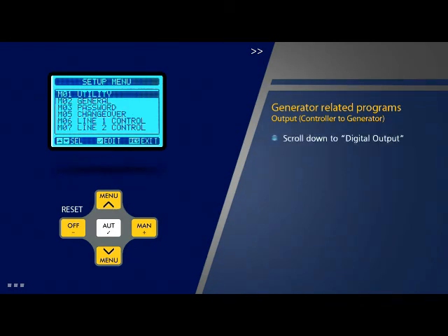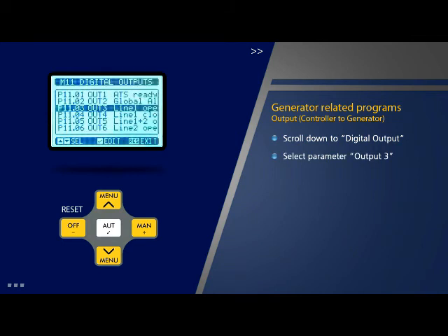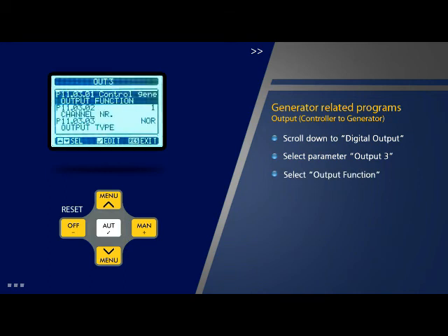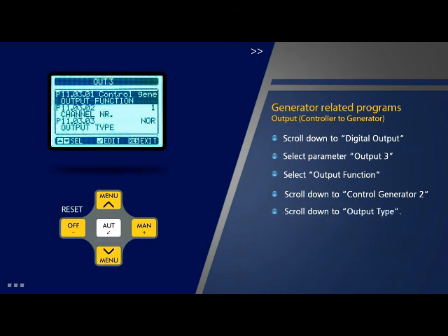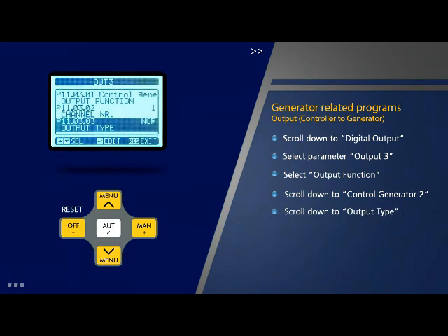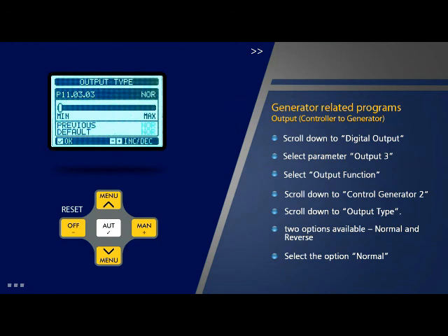Scroll down to option 11 'Digital Output' on the setup menu page and press OK. Select parameter 3 which is 'Output 3' on this page and press OK. Select the option 'Output Function' which is the first option on this page and press OK. Scroll down to select the option 'Control Generator 2' and press OK. Come back to the output 3 page and scroll down to parameter 3 which is 'Output Type'. Two options are available: normal and reverse. Select the option as per site requirement, for example 'Normal', and come back to the previous menu.